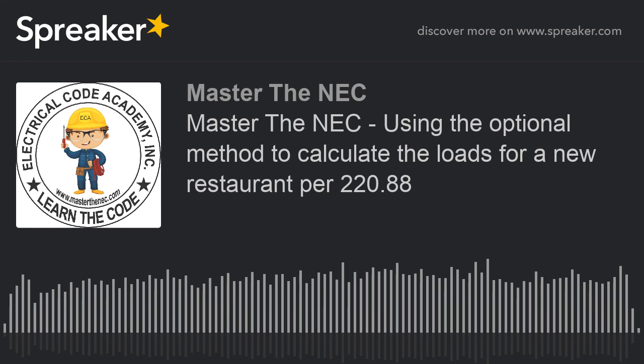So that's why we put this service disconnect up. Now, that's just a service disconnect. On the load side of that service disconnect, there's no other loads being served out of that service disconnect except for the feeder that's feeding a remote distribution panel downstream, just like the owner wants. Now, that is a feeder. But since all of the loads for the actual restaurant are going to be coming out of that downstream remote distribution panel, that feeder that's coming from the service disconnect to that downstream remote panel is considered a main power feeder, even though we don't define it as that anymore.